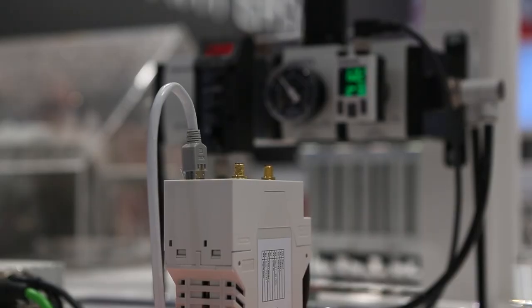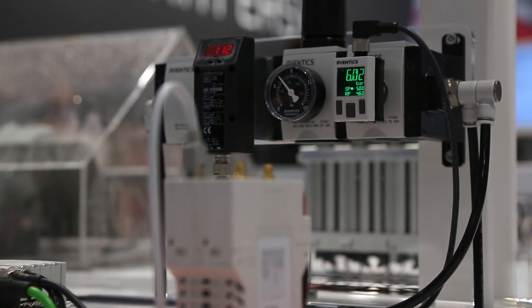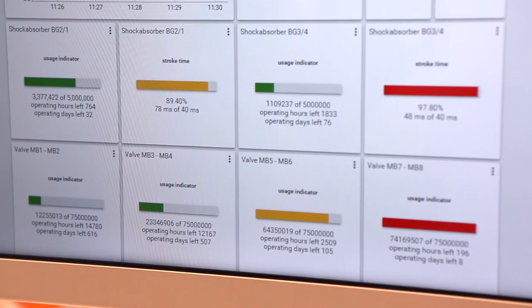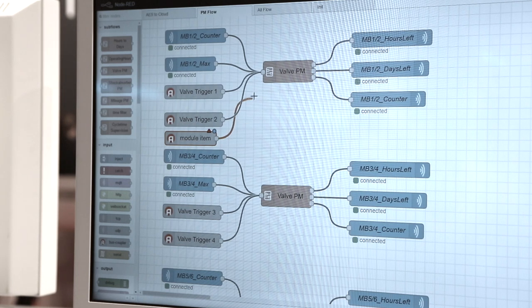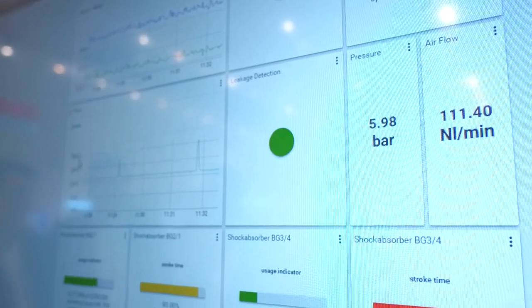For example, to monitor the wear of a shock absorber, the SPM breaks down the end-switch signals to evaluate the cushioning sequence. Algorithms written by Aventics based on the company's application experience analyze this data internally and send the information either to defined people or to the parent MES or ERP system via the OPC UA interface.